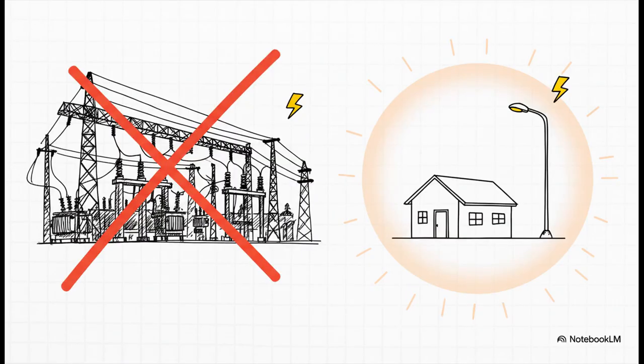And let me be really clear here, this isn't just some crazy high voltage substation problem. We're talking about your standard low voltage system, the 230 or 240 volts that power our homes and our streetlights. That's more than enough to create a fatal touch potential during a fault. It's a serious risk we have to deal with everywhere.